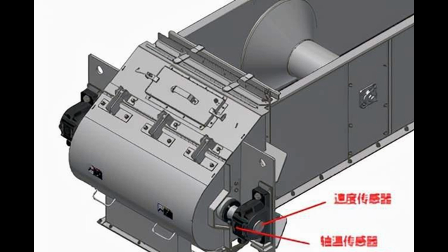9. Protection devices along the line. The function is to artificially stop the operation of the conveyor in any part of the belt conveyor and control the occurrence and expansion of the belt conveyor accident in time. Common protectors along the route are the push-button type protector. One emergency stop button is installed every 40-50 m, and is connected to the belt conveyor automatic control system.